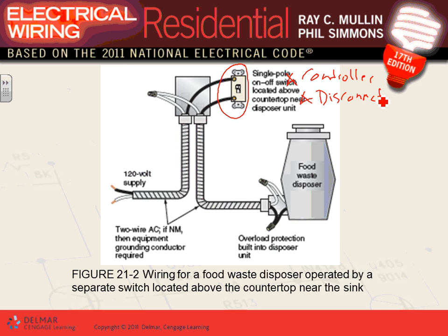And from this end, what do you do? You go over here and you put your 20 amp circuit breaker, and here's my neutral. This is what we call a hardwired garbage disposal. No problem. Bring it on. No receptacle. The way you guys did it with me is with a receptacle. I like it with the receptacle. The nice thing about the receptacle is you can unplug it.